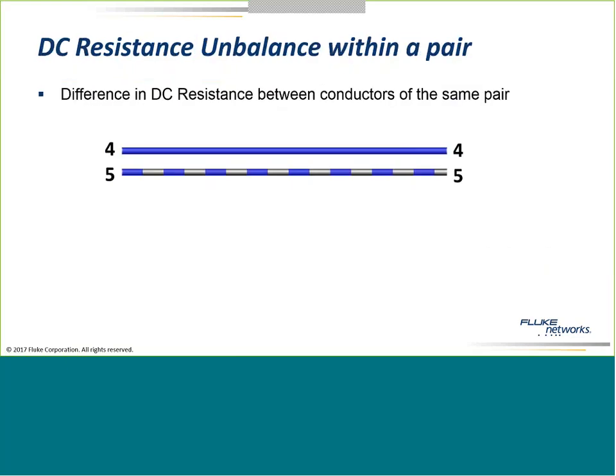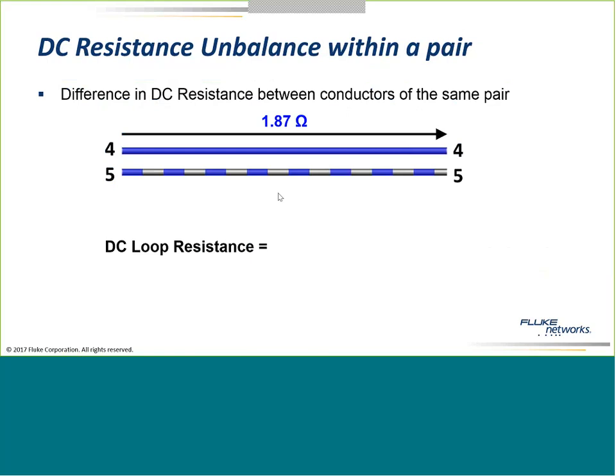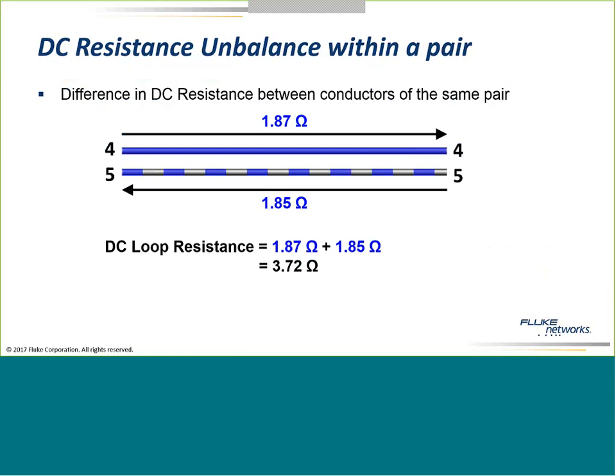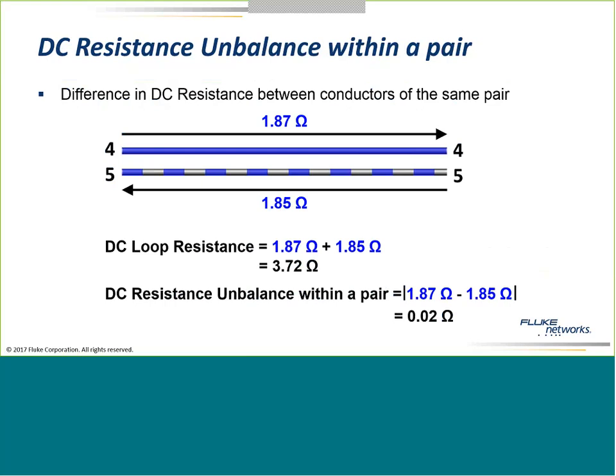What is resistance unbalance? First, let's look at what loop resistance is. We've got two conductors within a pair. The resistance of one leg of the pair plus the resistance of the second leg gives us the loop resistance — expressed in ohms. The higher the value, the more resistance, the more signal loss, the more effort needed for transmission. The resistance unbalance is the difference in those two values — we want the resistance for each leg of the pair to be similar.